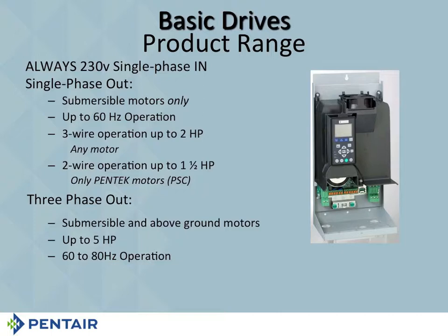So you can set it for 80 hertz. We're always going to recommend 60 hertz. And of course, part of the reason for that is wear and tear on both the motor and the liquid end. They're designed for 3450 RPMs. You are taking them up to 4800 RPMs. That obviously is going to shorten the life. So we prefer that you not do that, but we're not going to tell you you can't do it.